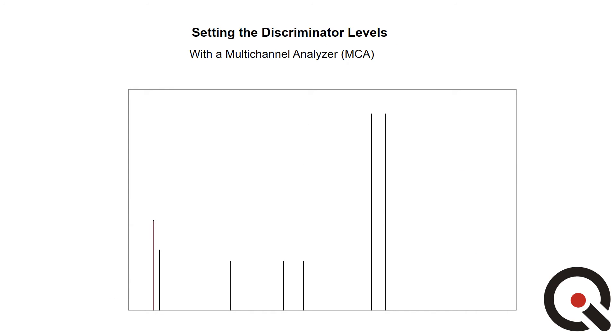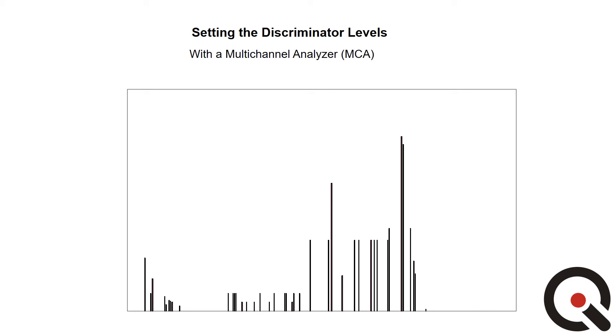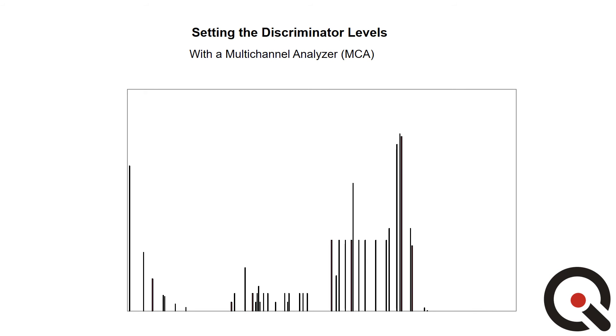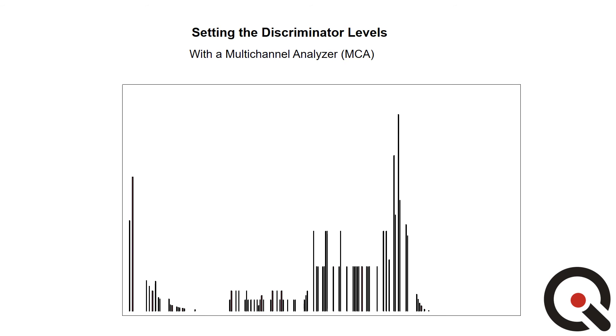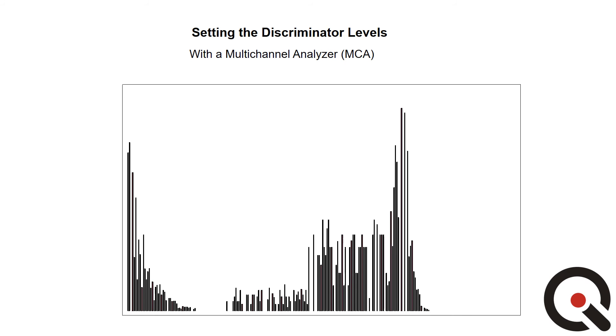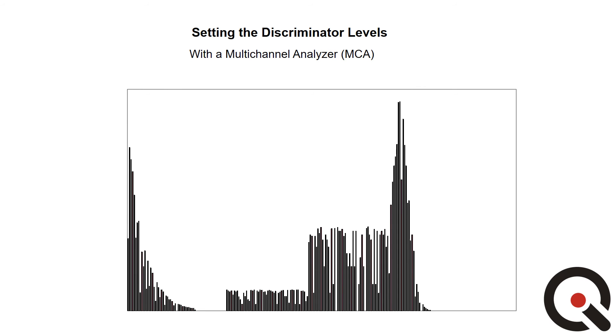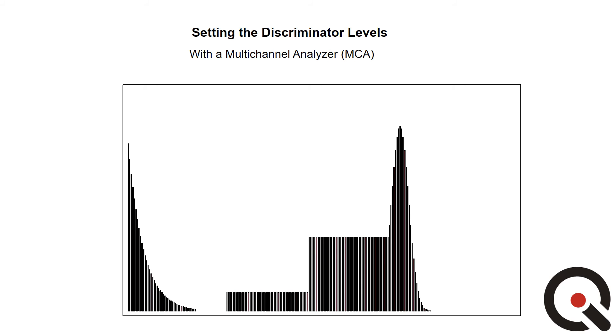However, with a multi-channel analyzer, the entire spectrum is visible and the user can see exactly where to set the discriminator values to maximize signal and reject noise. When using a multi-channel analyzer, the pulse-height spectrum histogram fills in over time and allows the user to visually identify features such as peaks and valleys. Clearly, using the actual pulse-height spectrum is a more direct and accurate tool in setting up your neutron detector parameters.